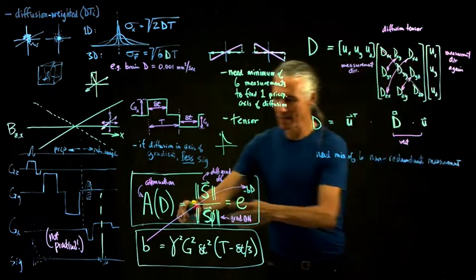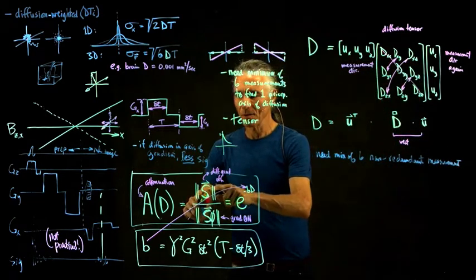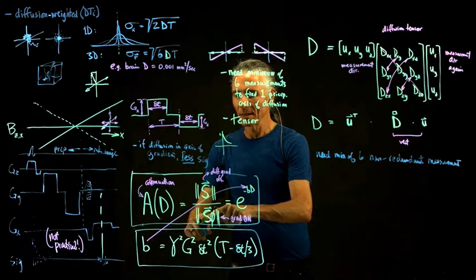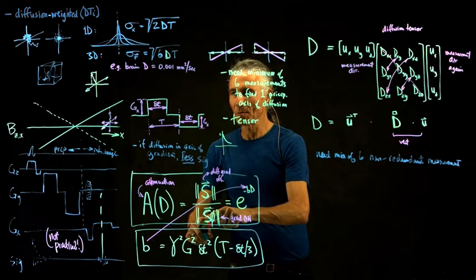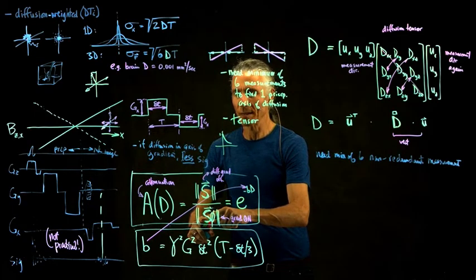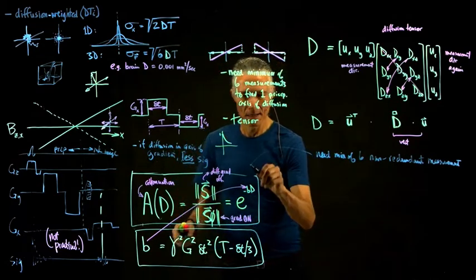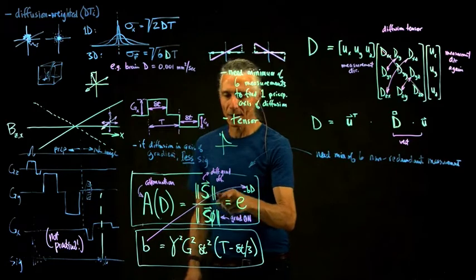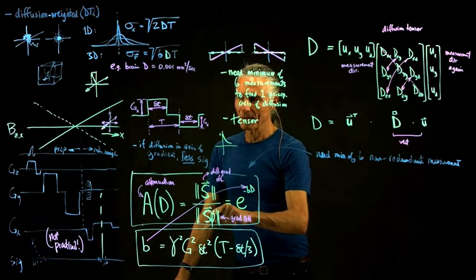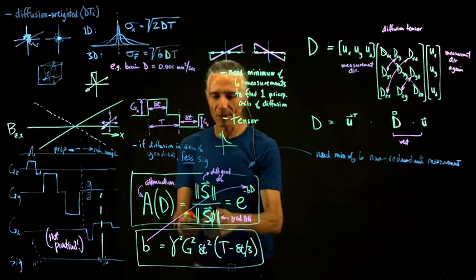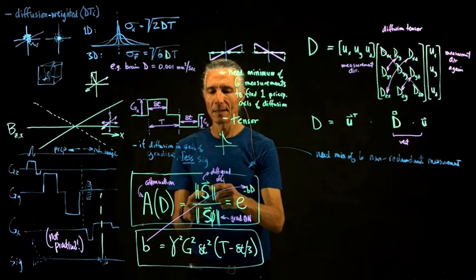Of this kind, where we turn the diffusion on in a particular direction, and then divide it by the image brightness that we get without the diffusion gradients on. So we need six measurements of these. We only have to measure the brightness of the image with the gradients off once. So typically we'll separately do this measurement and then do 6 different diffusion measurements.